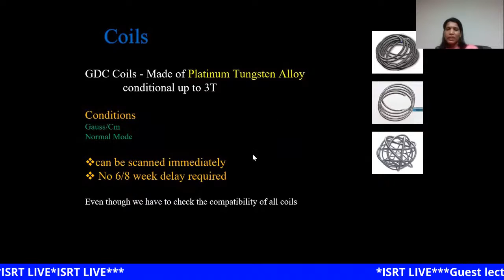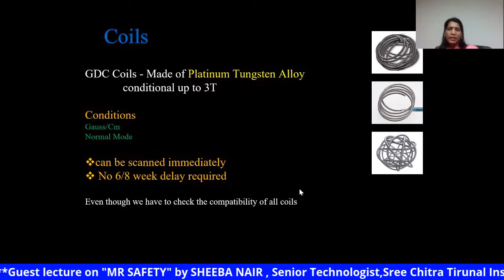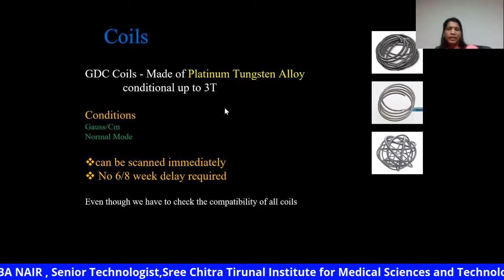Most of the coils that are available are MR compatible. So it is always better to check the compatibility of each coil separately. Even some coils, the GDC coils, are conditional up to 3 Tesla.